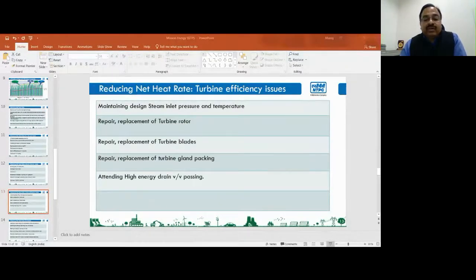We are addressing heat rate deviating parameters and taking corrective actions on a real-time basis, and we are bridging the heat rate gap between the design and actual values. In that software, monetary values are also shown, so that makes the operating engineer sensitive to the losses which are taking place in real time.